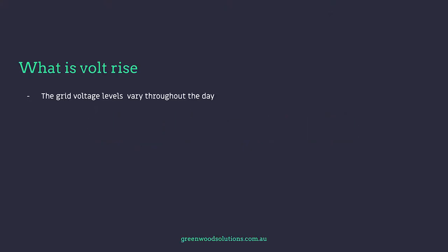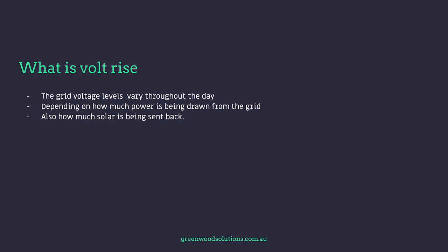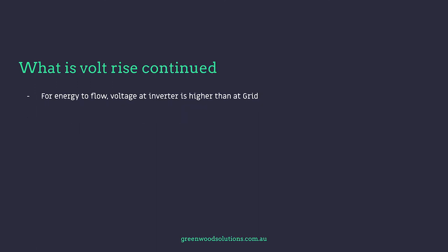The grid voltage levels vary throughout the day depending on how much power is being drawn from the grid, and also how much solar is being sent back to the grid. For energy to flow, the voltage at the inverter must be higher than at the grid, and issues can occur when cables haven't been sized correctly.